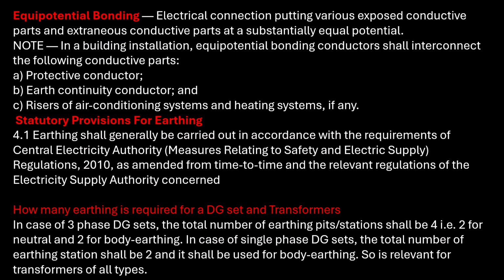Next set of definitions. First is equipotential bonding. Electrical connection putting various exposed conductive parts and extraneous conductive parts at a substantially equal potential. Note: in a building installation, equipotential bonding conductor shall interconnect the following conductive parts: protective conductor, second earth continuity conductor, and third riser of air conditioning system and heating system if any. Next, statutory provision for earthing.